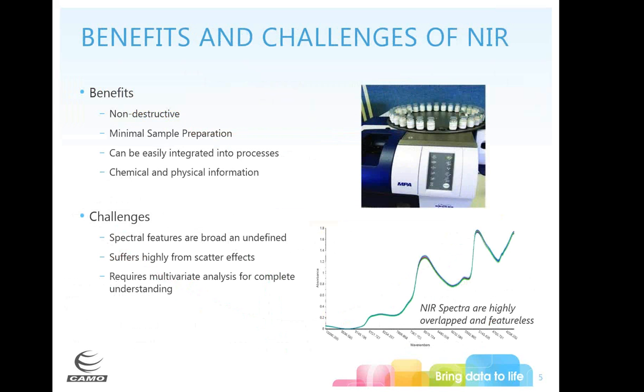Some benefits of using near IR: it is non-destructive, you don't have to do much sample preparation if any, it's easy to integrate into your process, and it contains both chemical and physical information. The challenges are that spectral features are very broad and undefined due to overtones and combination bands. You also have serious issues with scattering effects because the ratio between particle size and wavelengths are closer, so you almost always require multivariate data analysis to understand your NIR spectra.